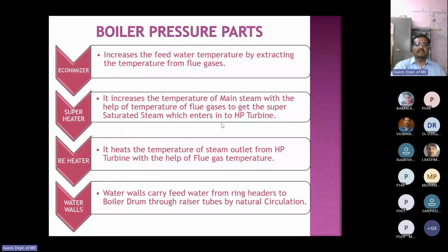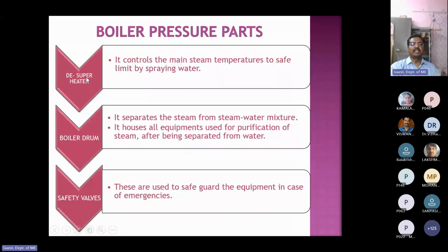The water walls are the tubes that surround the furnace. And the desuperheater: the purpose of the desuperheater is to reduce the temperature. For different utilities, low temperature and low pressure steam is required, for example during soot blowing or for ejectors. For that purpose we use the desuperheater. In the desuperheater, they spray feed water directly into the steam and reduce the temperature. Next, there are different safety valves arranged on the boiler for safety.